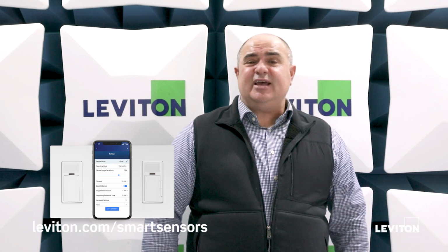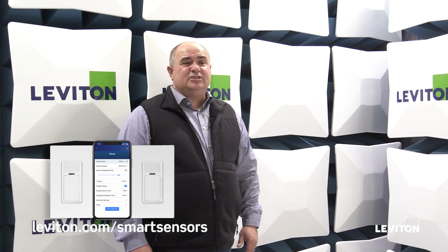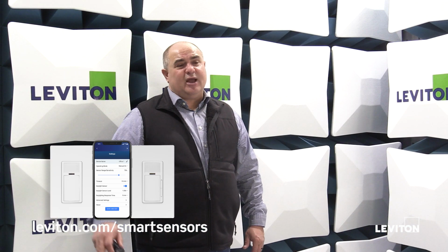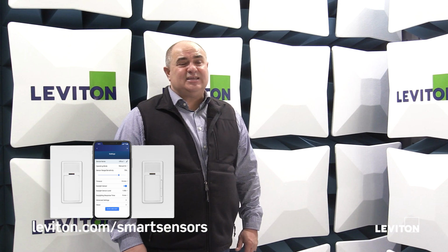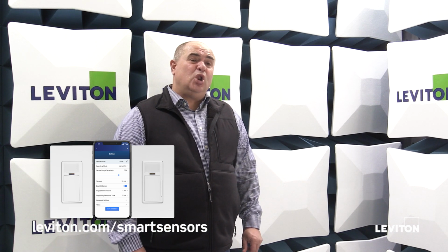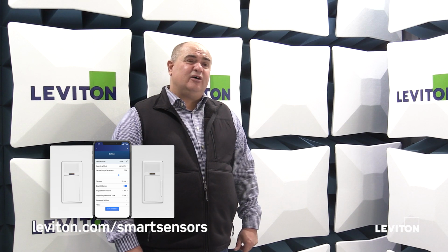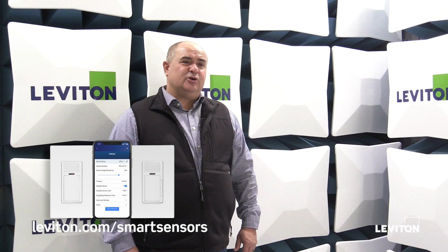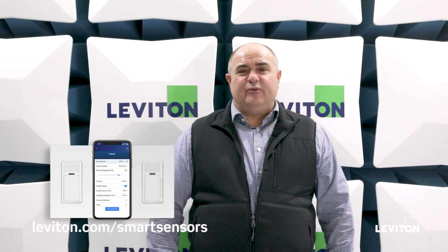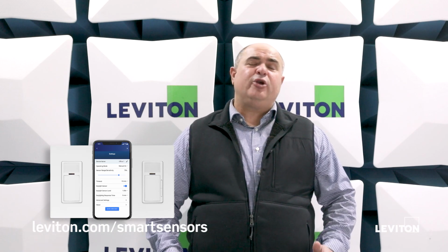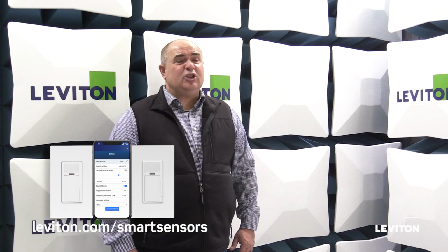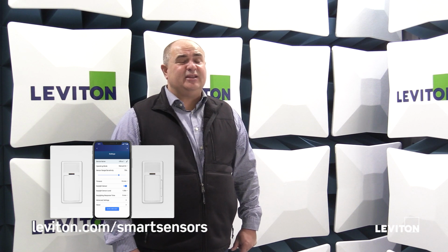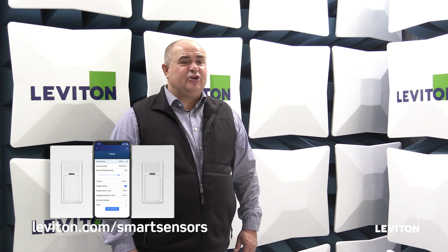So that all being said, as you look at your designs, the majority of the spaces that are, I would say, 500 square feet or less actually have well below those levels of wattage within the daylight zones. And one of the things I need to make sure we look at when we are looking at that wattage is that it doesn't take into consideration any of the other lighting in the space that are not considered general lighting.